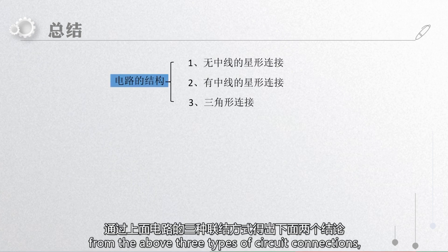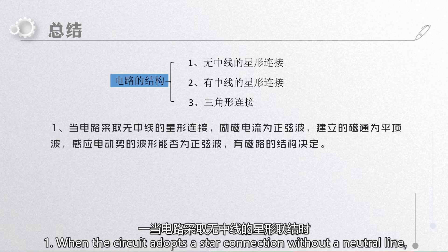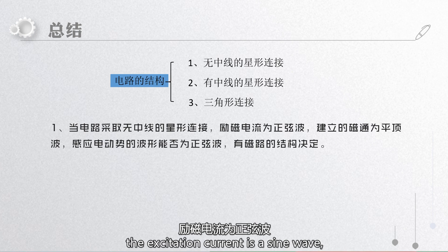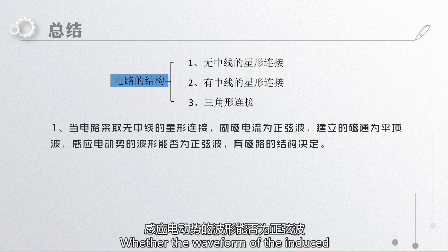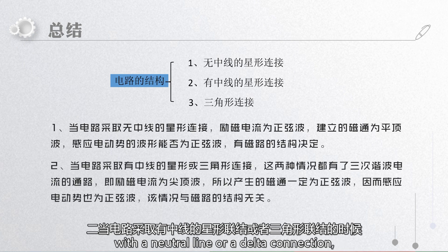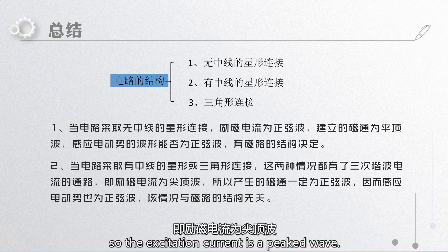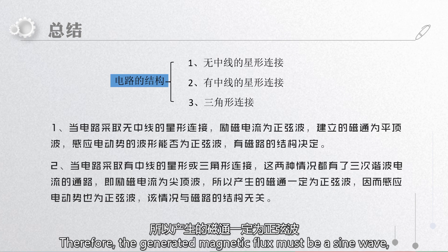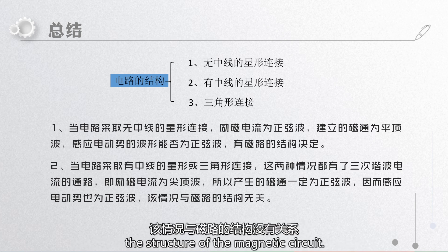In summary, from the above three types of circuit connections, we can derive the following two conclusions. 1. When the circuit adopts a star connection without a neutral line, the excitation current is a sine wave and the established magnetic flux is a flat-topped wave. Whether the waveform of the induced electromotive force can be a sine wave is determined by the structure of the magnetic circuit. 2. When the circuit adopts a star connection with a neutral line or a delta connection, both situations have a path for the third harmonic current, so the excitation current is a peaked wave. Therefore, the generated magnetic flux is a sine wave and the induced electromotive force is also a sine wave — this situation has nothing to do with the structure of the magnetic circuit.